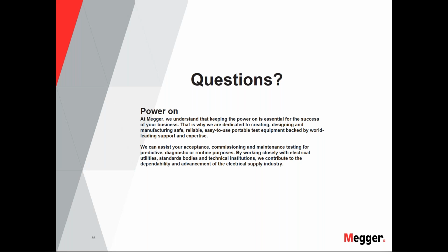Thank you. Next question is for Danabal. On what loading points should measured third harmonic for stator ground relay set points? Yeah, third harmonic measurement in general, even including IEEE standards, we measure on the 100%, is basically 1 per unit of the generator capacity. So for example, in a 100 megawatt generator, it may be close to 5 to 6 volts third harmonic generation that happens. All right, thank you.